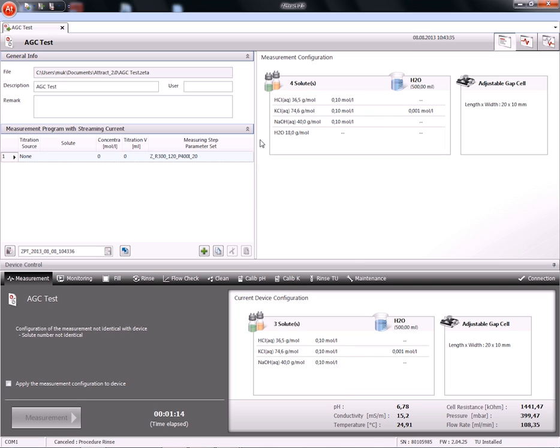In the measurement document view here, you are shown the different steps of the measurement. In our case, it's only one step. Under parameter set up here, you can define your target pressure and rinse time for your measurement, for example. The information is all contained in this one line here. There's a drop-down list of parameter sets, both predefined and customized.